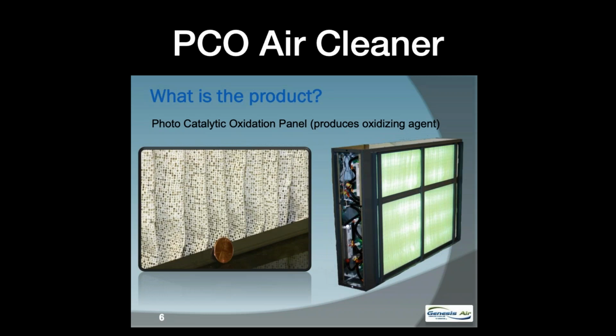If you look at the penny and the white media there, that white media is titanium dioxide. Titanium dioxide, when it's activated by UV light energy, UVC specifically, causes a reaction which creates what are called hydroxyl radicals. I refer to them as a vapor form of hydrogen peroxide. It's a highly reactive radical. And any VOCs or biologicals passing through that media where these radicals are created are destroyed, and going downstream, you've got CO2 and H2O.